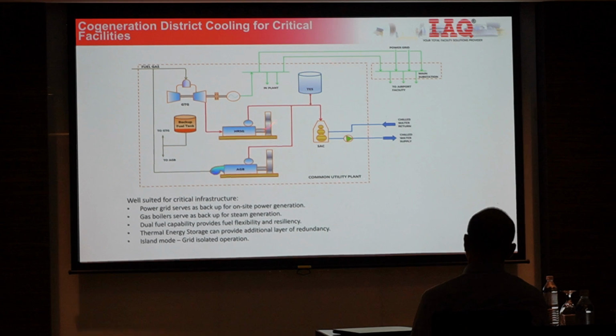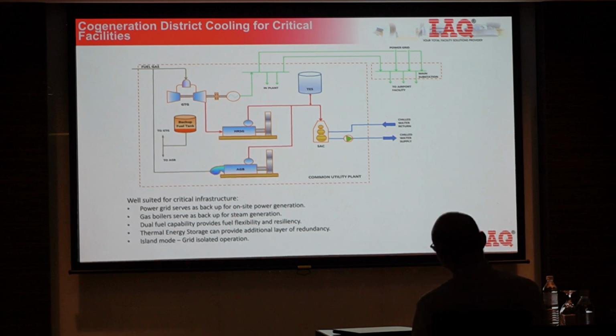For critical facilities that can't allow any downtime, we look at systems like a gas turbine with HRSG to generate steam, along with a backup boiler system. So in the event of a breakdown on the HRSG or gas turbine, you'll still be able to generate the steam required to power the steam absorption chiller.